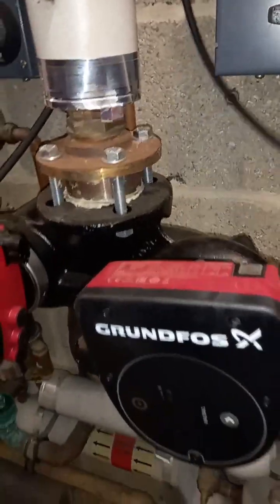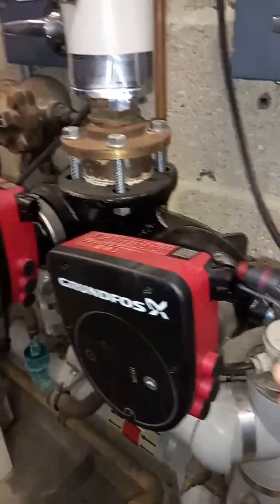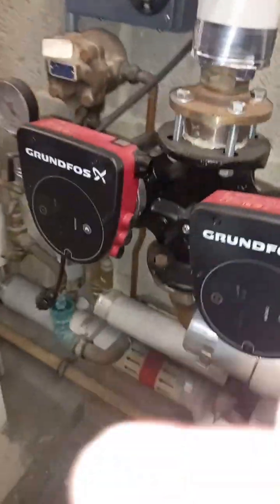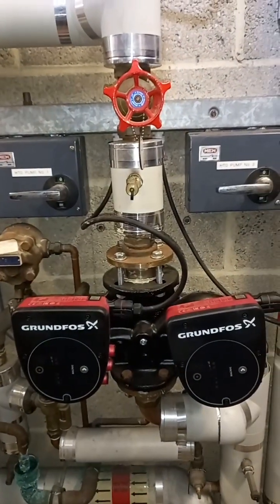I'm not seeing any leak come from the pump. I'm going to test them one by one, so I'm going to pop this in and turn them on to see what I get — see if it trips anything. I've got one and two connected up, and I'm going to look in the panel to see if anything's tripped.